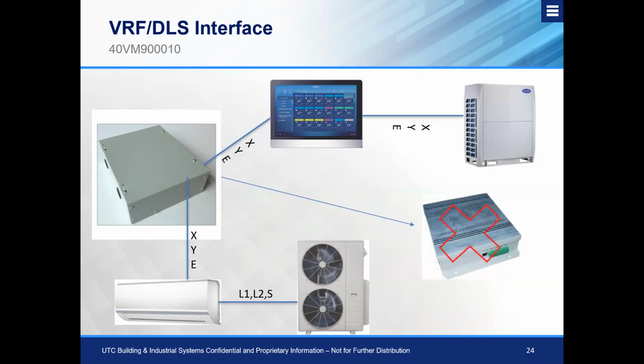One thing that I commonly get asked about these VRF and ductless interfaces is whether this can bring us into BACnet, and that is not the case. This device will not convert Carrier protocol over to BACnet protocol. We do have a specific BACnet interface that was recently introduced for ductless indoor units to bring them onto a BACnet native system, but this VRF ductless interface would not be the device that we're looking for.